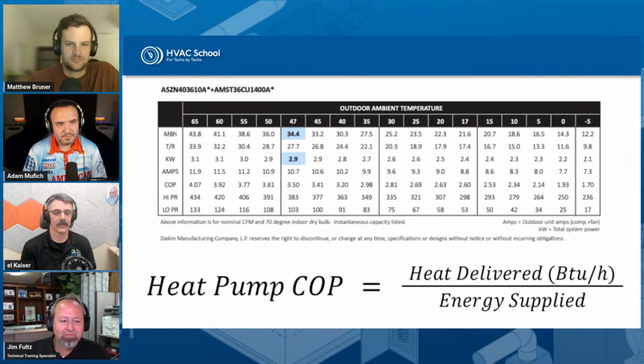So COP is coefficient of performance, and the whole point of writing the tech tip was that across the entire country we were seeing a pretty big cold snap, right? And I saw on different Facebook pages and forums, contractors, builders, all kinds of advice going around for people with heat pumps to switch your heat pump over to emergency heat. I think there's a big misconception of when you should use emergency heat and how you should set up a heat pump. That was my thought process behind writing the tech tip, which is good COP, bad COP. I like that.